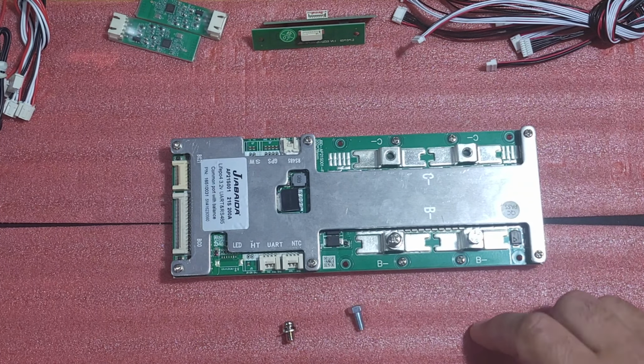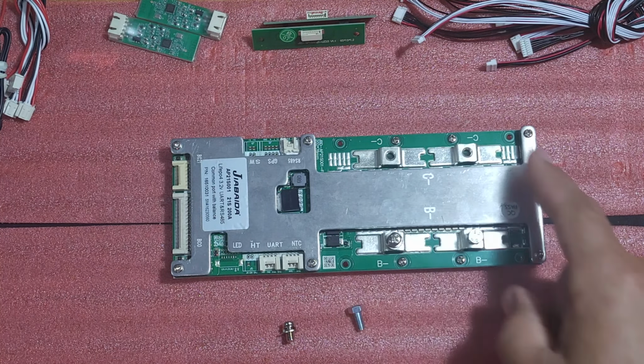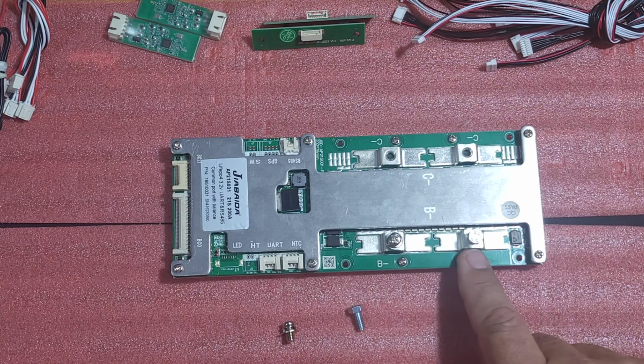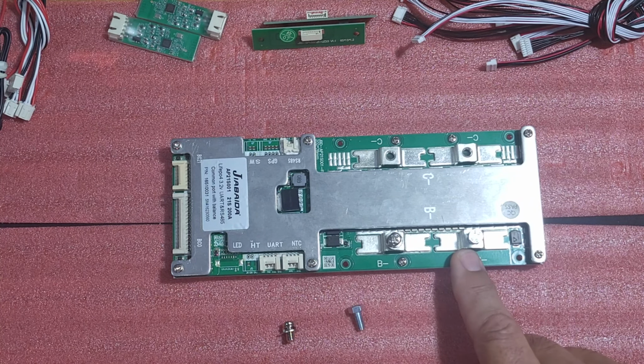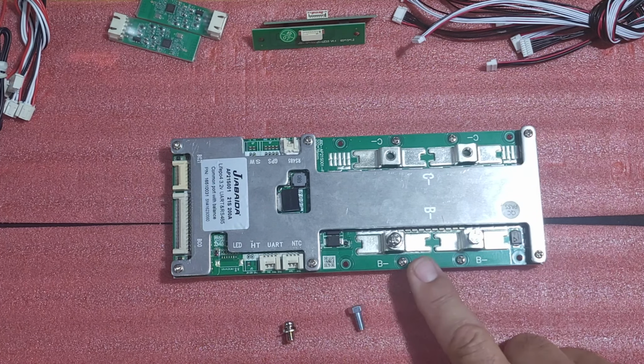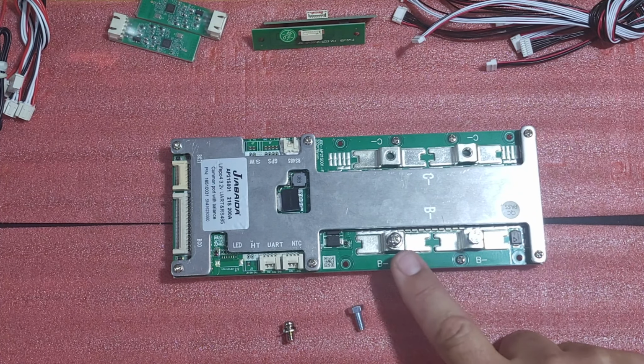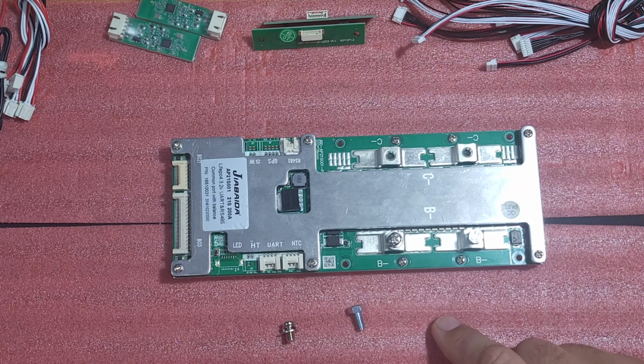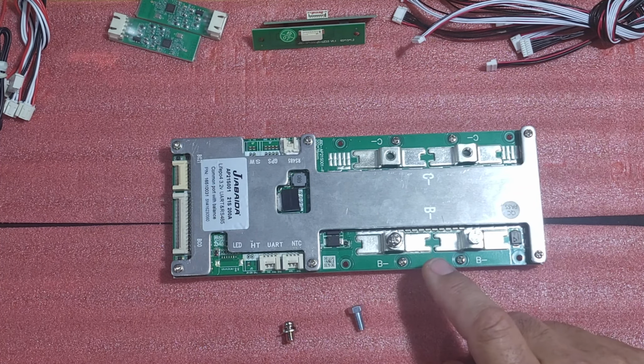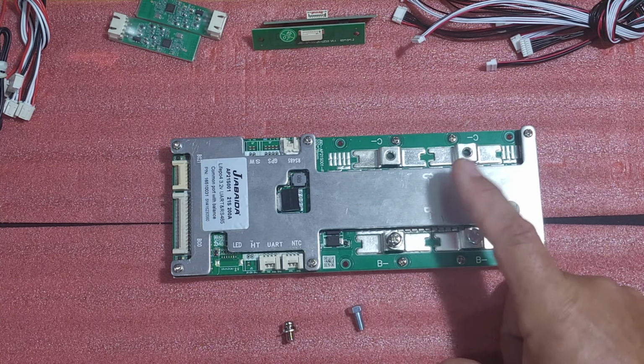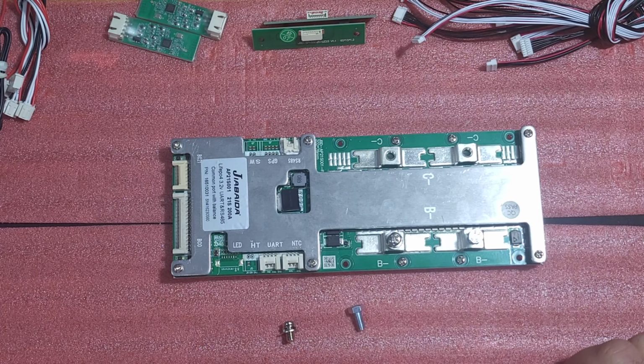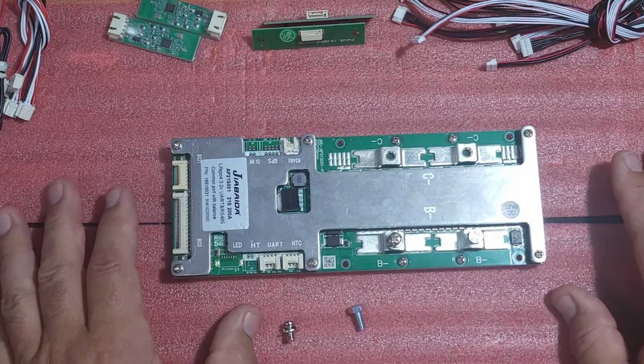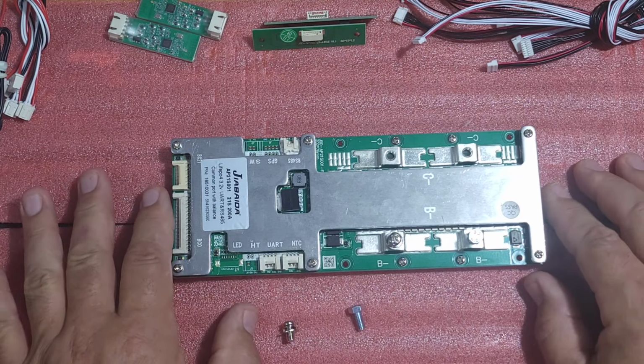So my thought is, why not jumper these lugs here at the BMS with the bus bar? So what I'm going to do is I'm going to get some 110 copper stock and create my own bus bar to jumper these. And what that'll allow me to do is the one single wire that comes off the bus bar, I can use a larger M8 bolt and run one single larger wire off of each of the lugs. So I'm going to go ahead and mock that up and see what that looks like.